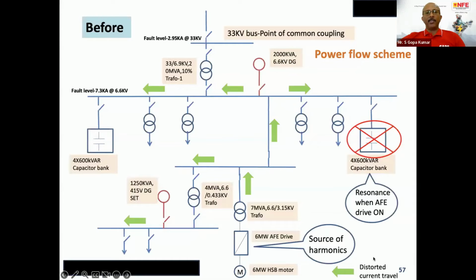So here, this is the typical power distribution scheme for heavy industry, where there is a testing facility where an active front-end drive is used. You can see at the bottom a 6 megawatt active front-end drive at the medium voltage level. This is fed by a 7 MVA transformer. Due to some tuning issues, this drive was producing distorted current, which we call harmonics. Now these harmonics started traveling across the power distribution network, depending on the internal impedance of the circuit. But at the upstream side, at the main substation, you can see there are two installations of 600 kVAR capacitor bank. One is here, one is here.